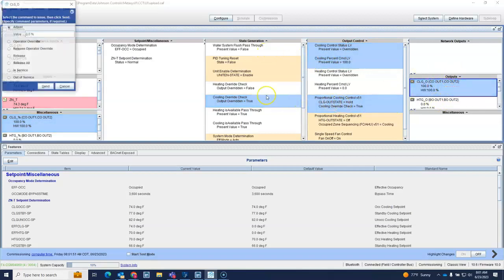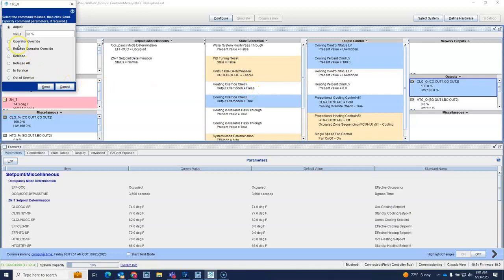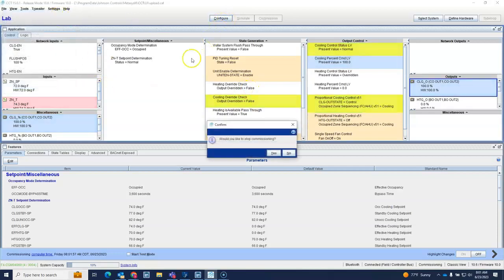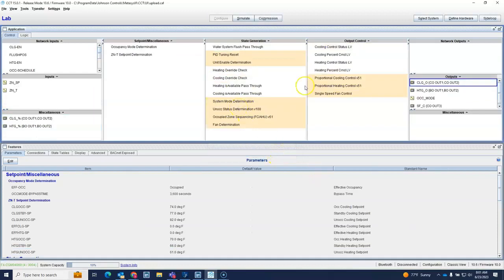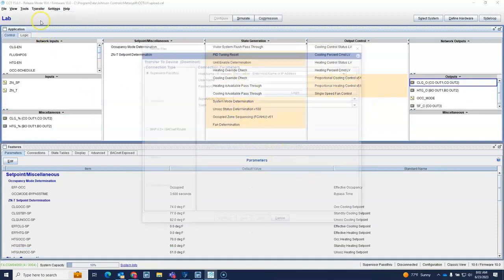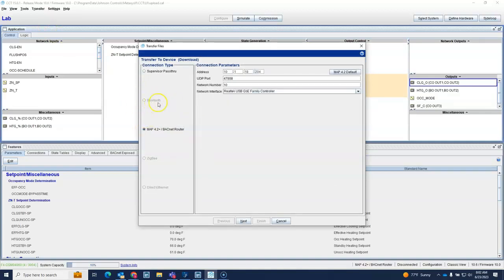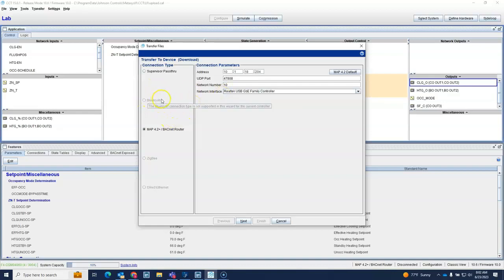But the downside to this is when I go, if I needed to make some changes in here, I go to transfer the device, I can't transfer the device. Now this is a CCT issue, it's not that tool. So if Johnson releases a new version of CCT that allows the Bluetooth to work again, then we would be able to Bluetooth download to the controller.